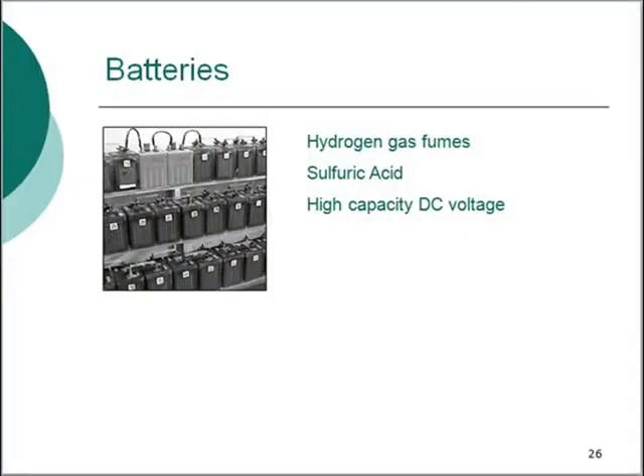During the charging process, hydrogen gas is emitted. For this reason, do not smoke or introduce flames or other sources of ignition. The battery cells contain sulfuric acid and distilled water to form the electrolyte. The acid is extremely corrosive. The batteries store a high-capacity DC voltage and current. Never let any part of your body or tools make contact between the battery terminals.